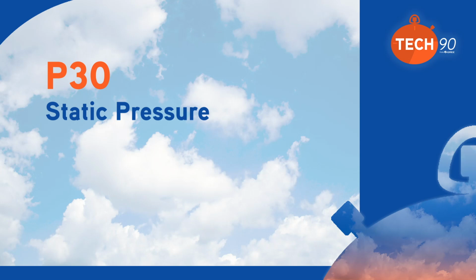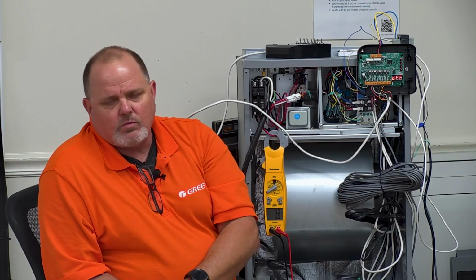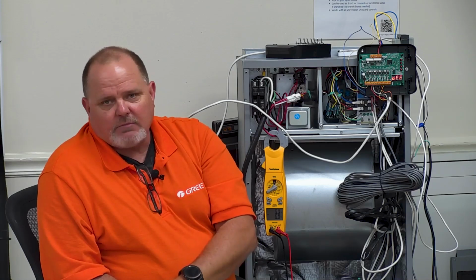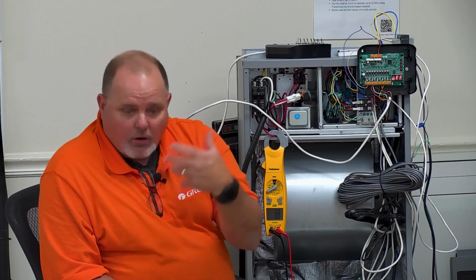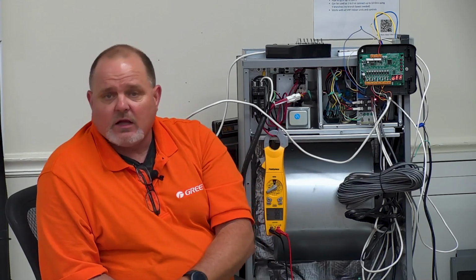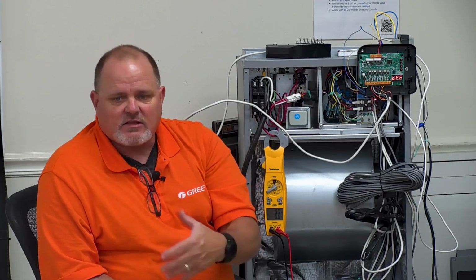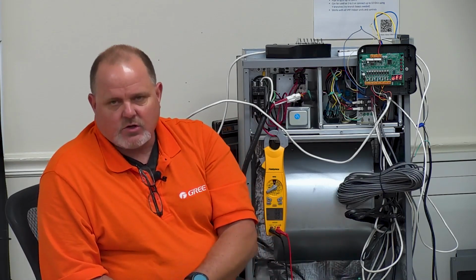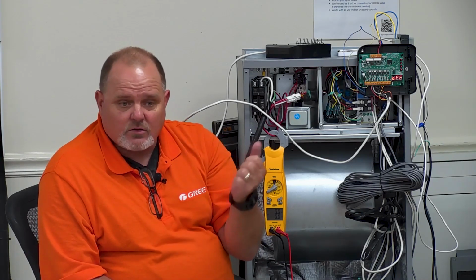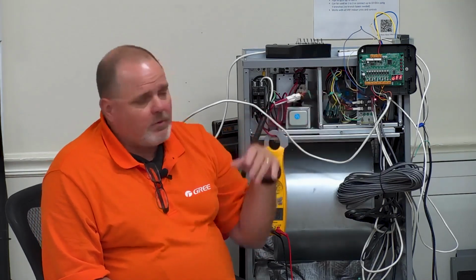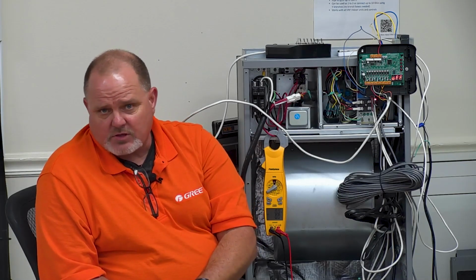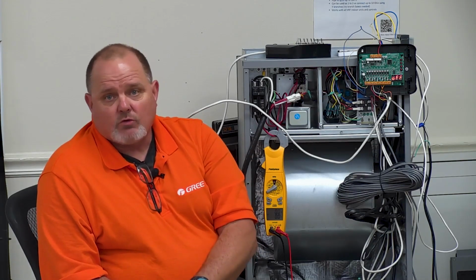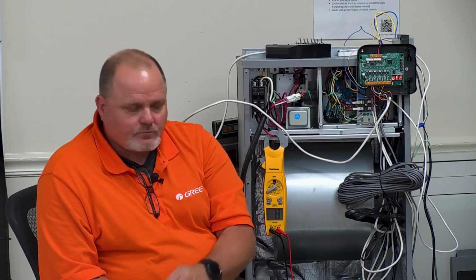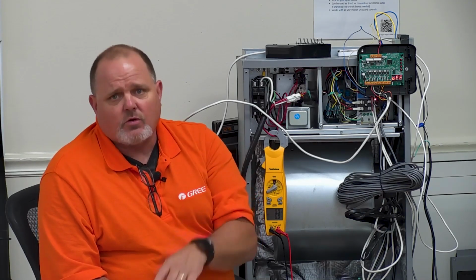We got static pressure, that's P30. So just like the GREE controllers, you have a static pressure setting for your blower between 1 and 9. 9 meaning you're giving the blower more thump, more hump to be able to overcome higher static. And a lower setting is going to be less thump from the motor at a lower static. So the way I tell guys to do this is you should measure it, okay? Start out, I believe the default is going to be static pressure setting of 5. So get the fan running on high speed. Once you get the fan running on high speed, measure your total static drop.